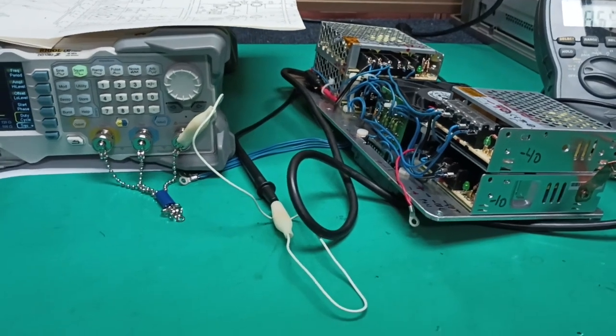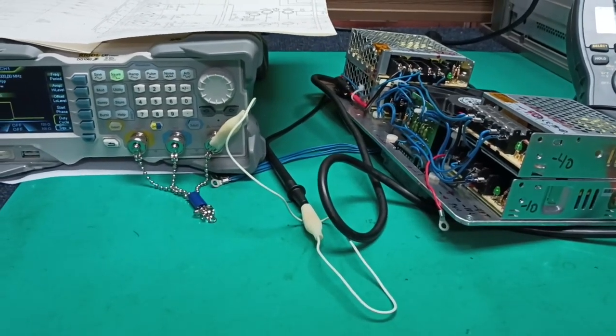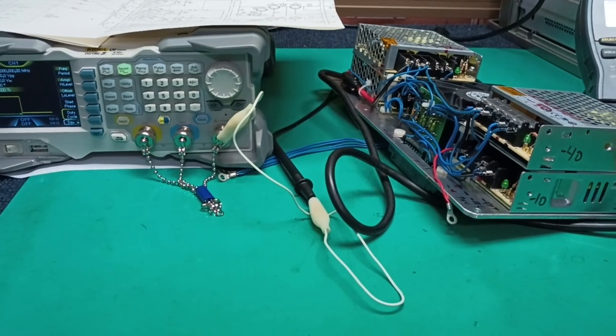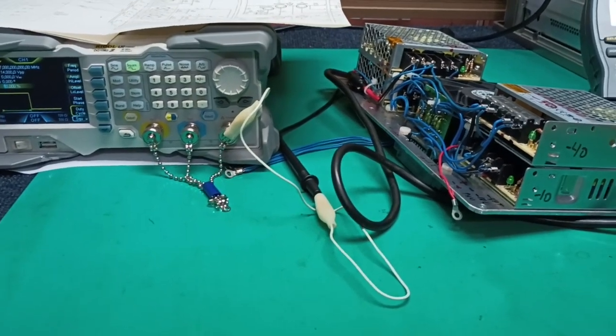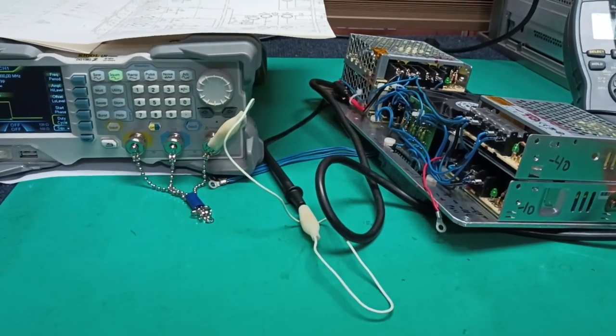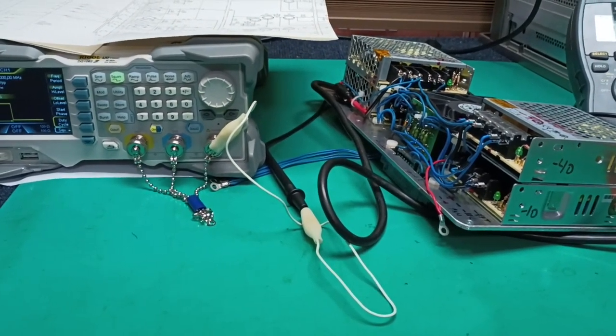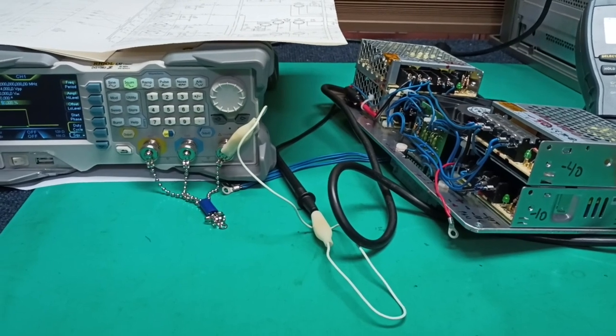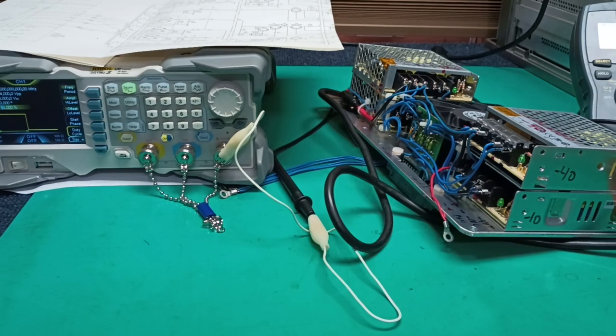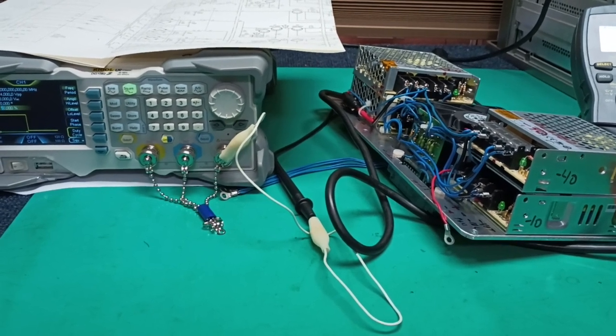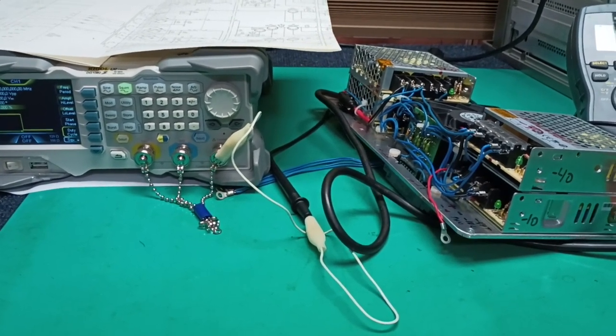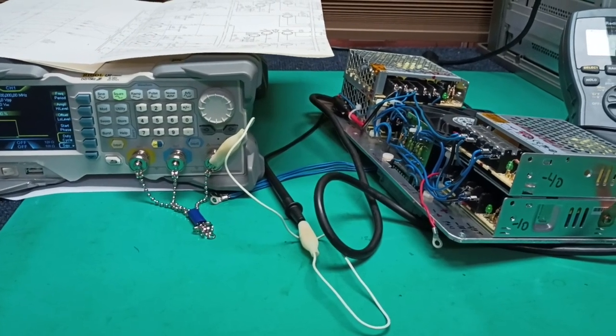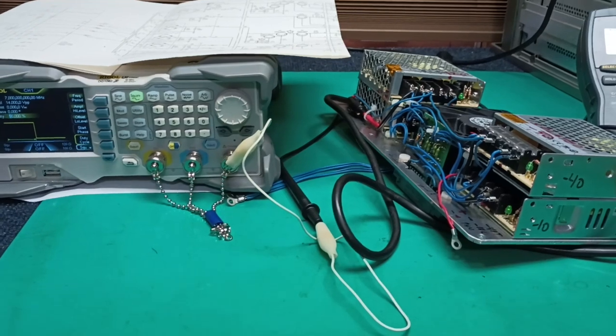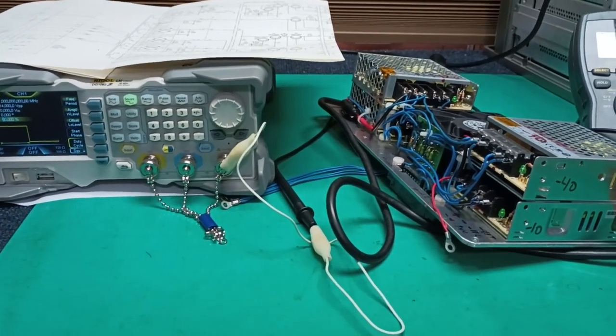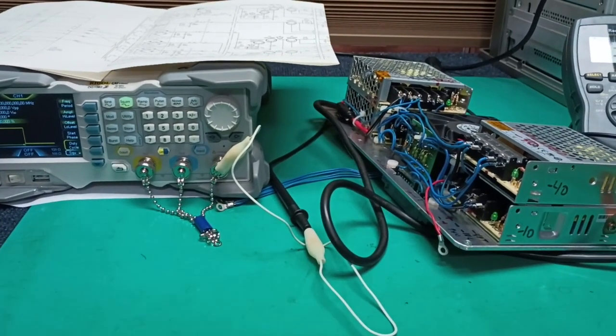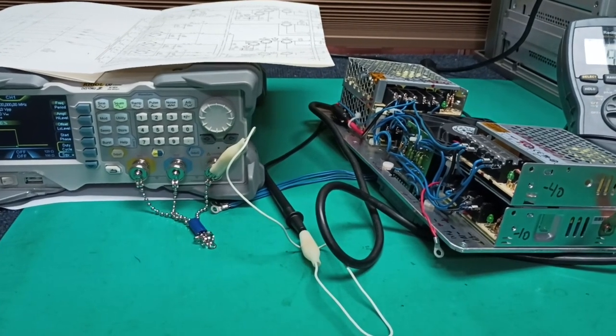So the common practice is said to be grounding the equipment together, and that is a very bad term, because what controls grounding is the National Electrical Code in the U.S. NEC says that ground is always and only the earth, and we are forbidden by code to earth ground anything in this room that's not at the service entrance. NEC 250.4(A) says we may not reground the load.